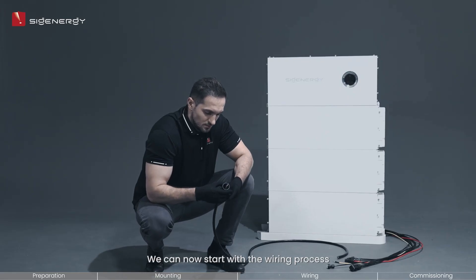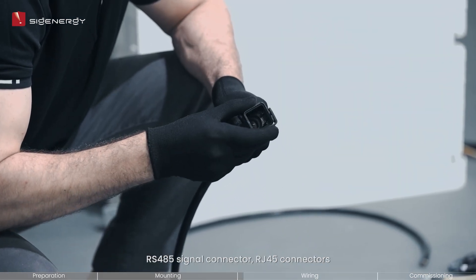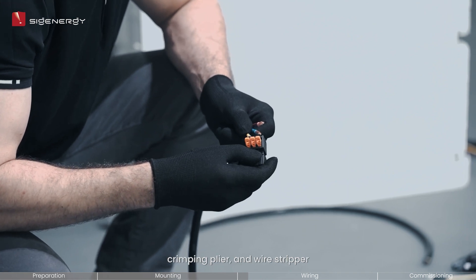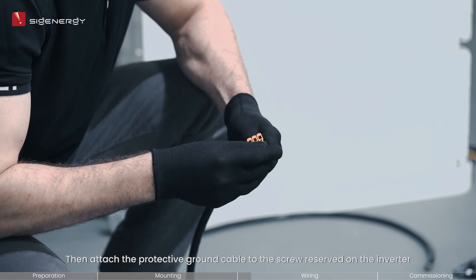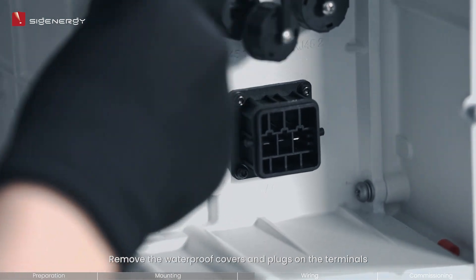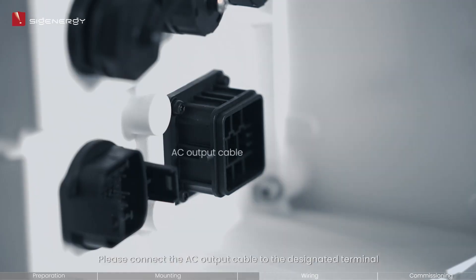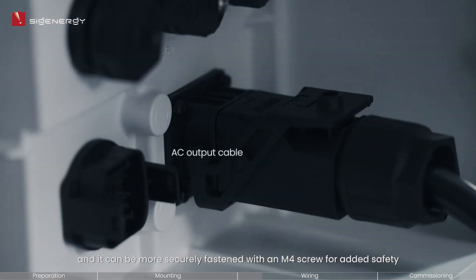We can now start with the wiring process. Prepare and assemble the AC output connector, RS-485 signal connector, RJ45 connectors, DC input connectors, and protected ground cable lug by using the wire cutter, crimping pliers, and wire stripper. Then attach the protected ground cable to the screw reserved on the inverter. Remove the waterproof covers and plugs on the terminals. Please connect the AC output cable to the designated terminal; it can be more securely fastened with an M4 screw for added safety.